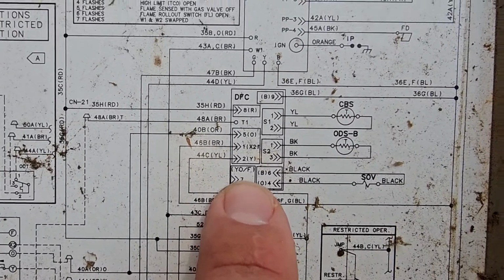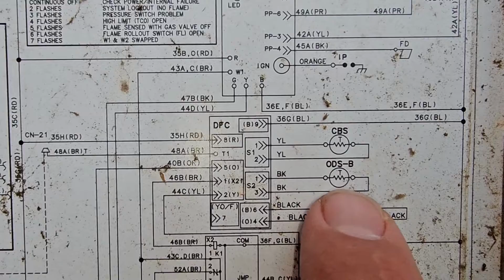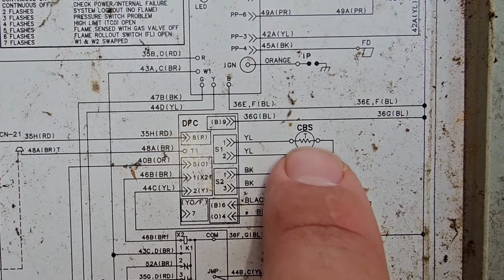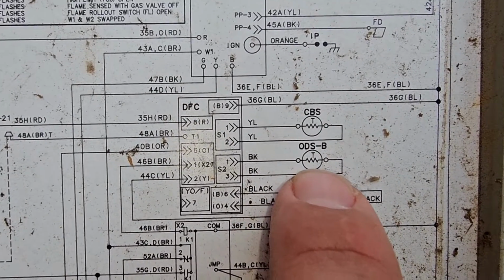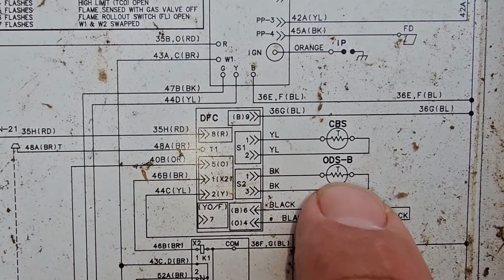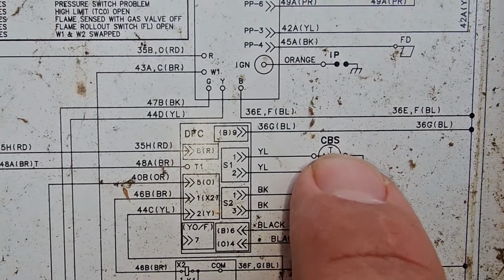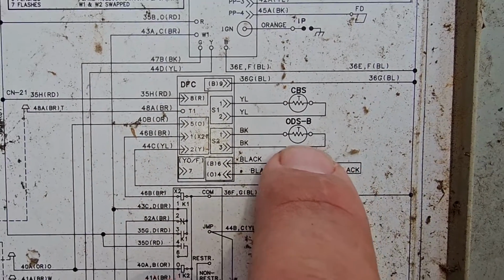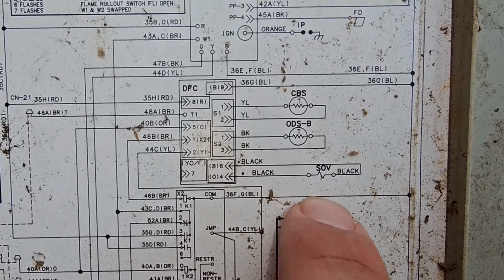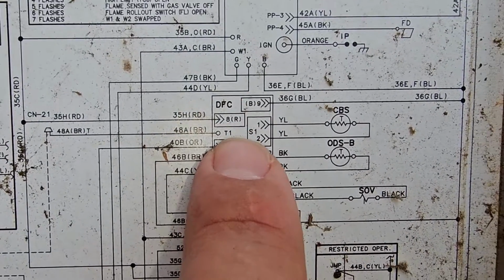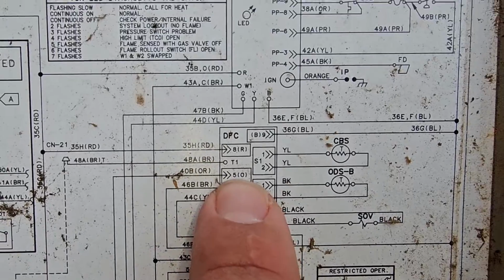For the defrost control, we've got CBS and ODS-B - coil bottom sensor, and outdoor sensor. So one sensor measures the coil temperature and one sensor measures the outdoor ambient temperature. If you don't know anything about defrost controls, I've got a video to learn more, and I'm going to put that down below as well for you.